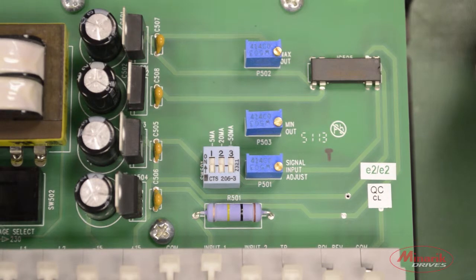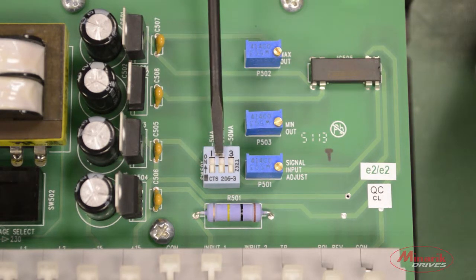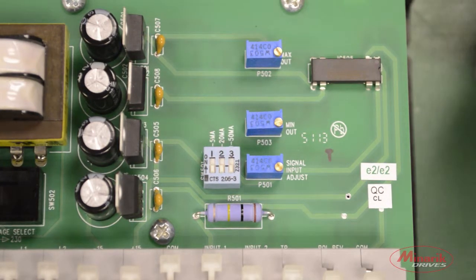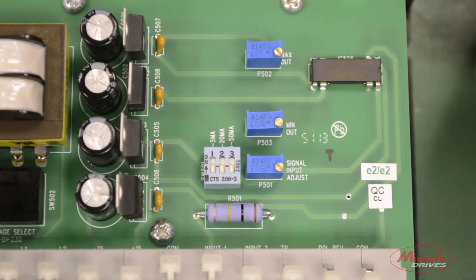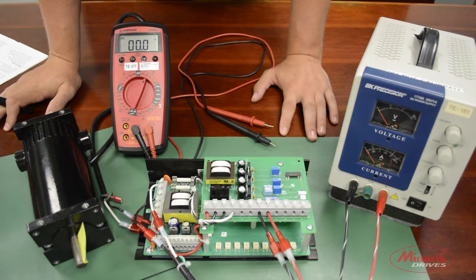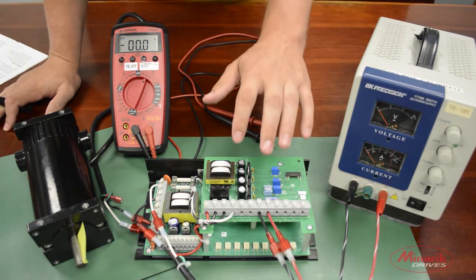Next, we'll look at the dip switches located in the middle of the isolation card. The factory default setting is for the dip switches to be in the off position. This sets the isolation card to accept an input voltage signal. If you're using an input current signal, please refer to your manual for the correct positioning of the dip switches. Now that we've finished wiring up the drive, we have to calibrate the isolation card.